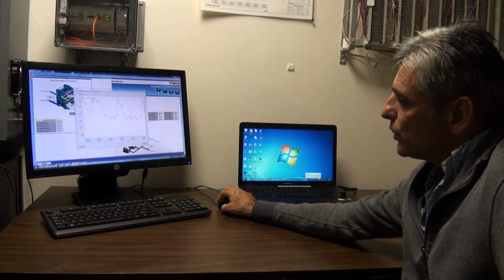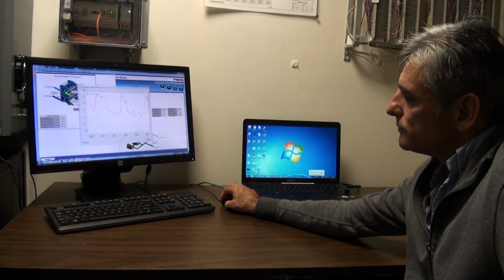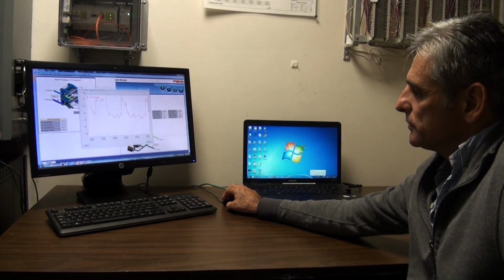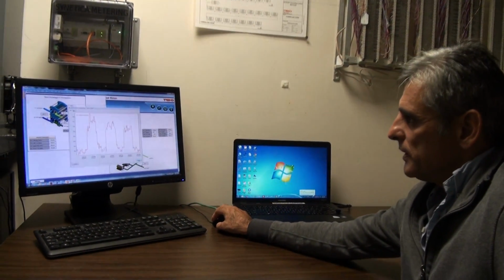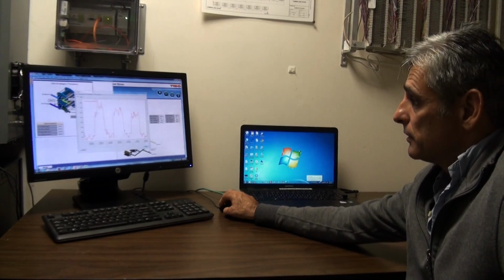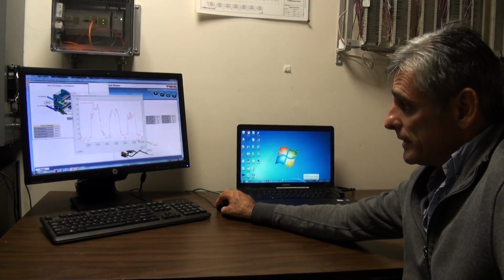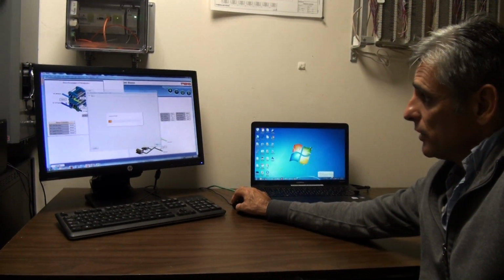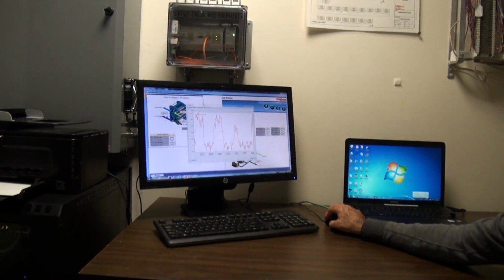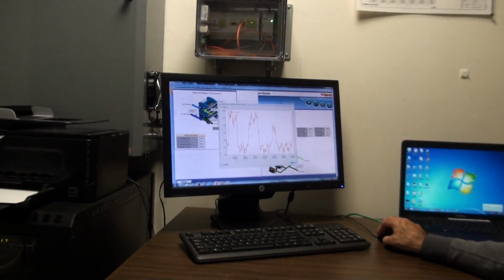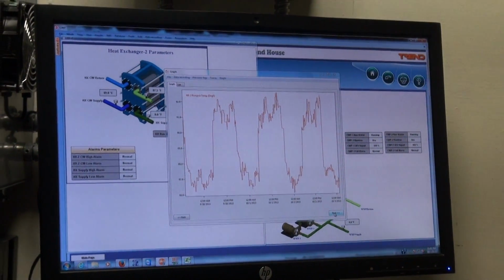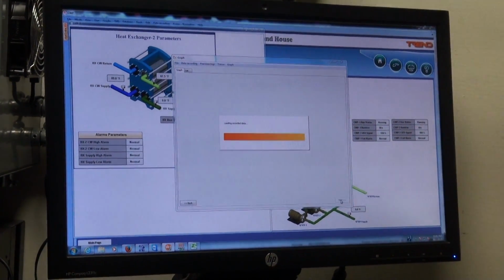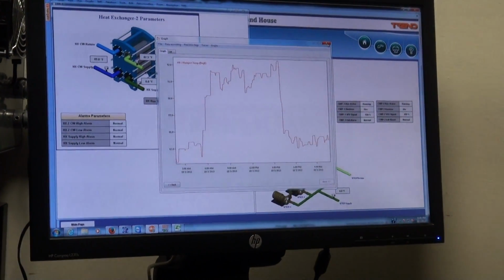A few weeks ago we installed a special bacteria eating system which stops the heat exchangers getting dirty. This was just installed a couple of weeks ago, and it's already showing temperature drops over the previous month. So it's working quite well at the moment. So that's that.